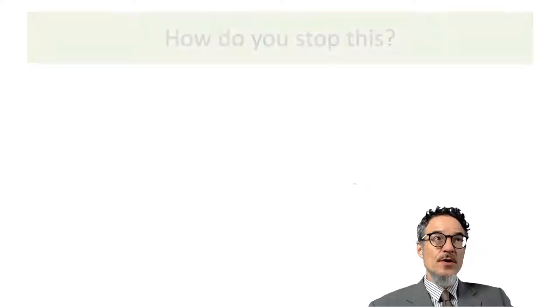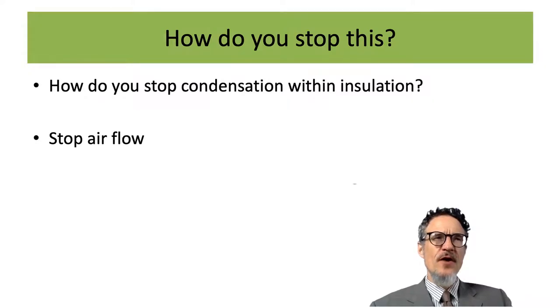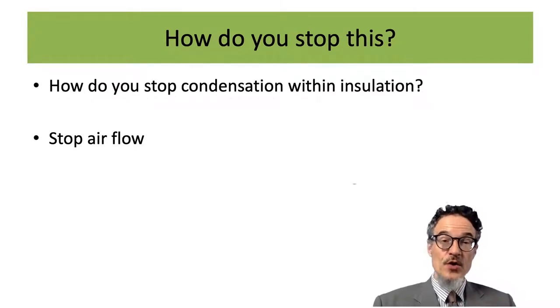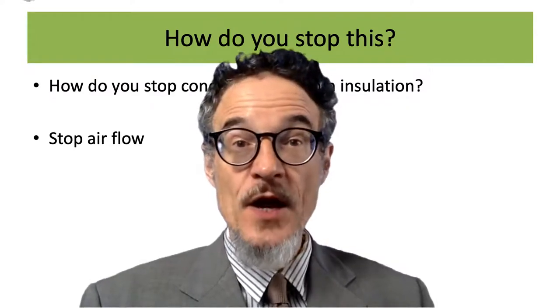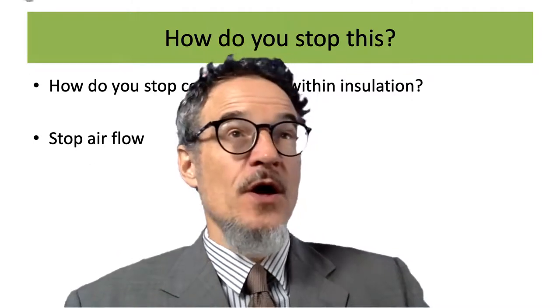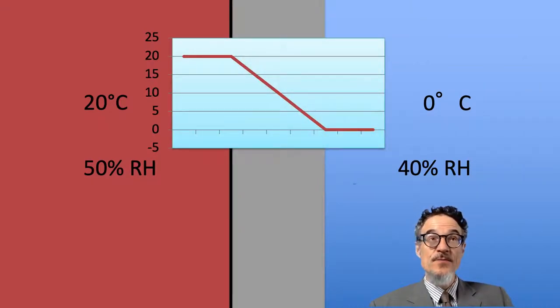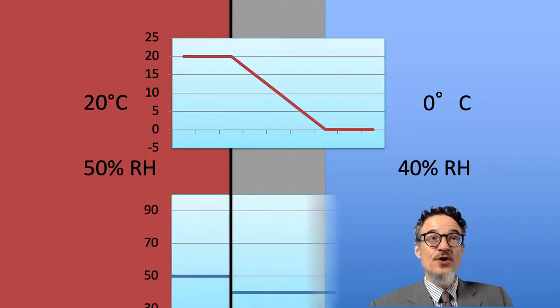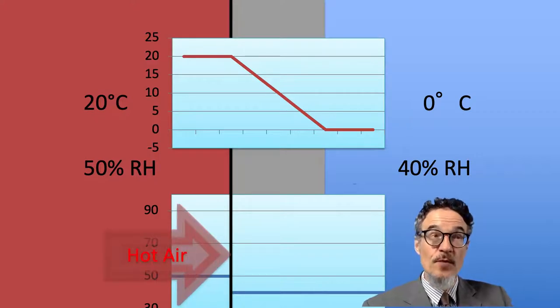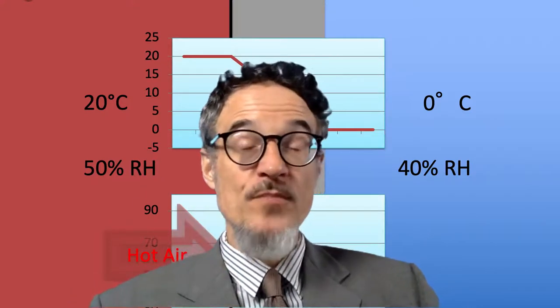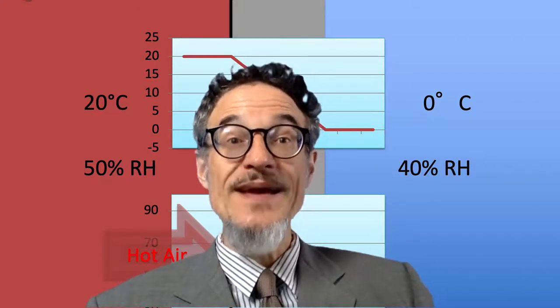How do we stop condensation within insulation? We need to stop the airflow. The reason we get condensation is because hot air is moving through the insulation out of the building. So we need to add a vapour barrier. With a barrier in place, we still get the nice temperature gradient, but we stop the hot air from passing through the wall, so we don't get high humidity inside the wall. Airtightness is very important — if we're going to have insulation we need to stop the air, otherwise we'll get condensation and water building up inside the wall.